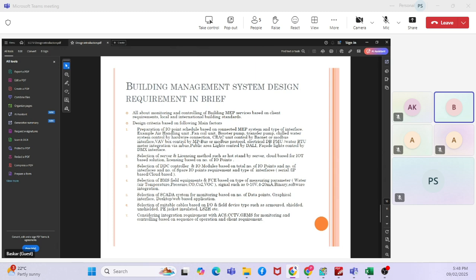Now, when we select the DDC controllers and IO modules, DDC or direct digital controllers have inbuilt IO points. Apart from that, some brands come with expandable IO modules or fixed IO modules. Based on the specification, it may limit one DDC controller or one DDC panel to a maximum of 50 IO points. Then we need to limit our design to 50 points. If more than that, we need to consider additional DDC panels. And then there is the selection of field equipment, which we select based on the system we are monitoring and controlling.